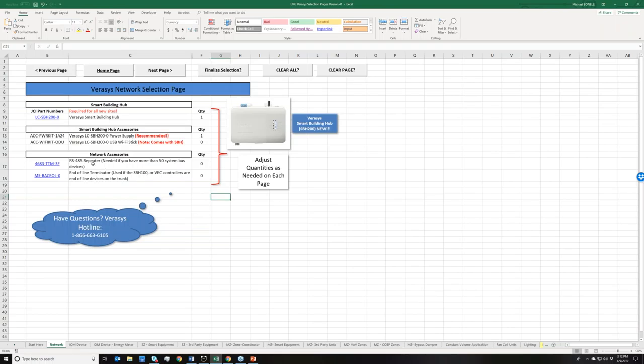We had some other items in previous documents, such as wiring. Wiring can be sourced from a bunch of different locations, so it's not part of this document moving forward—it might become part of it later. The two major accessories we have are a BACnet repeater and a BACnet end of line. Not all of our Verasys controllers have a built-in end of line, so you may need one. I try to call out which ones don't, so you can know when you're actually sizing the job. And then there's the repeater.